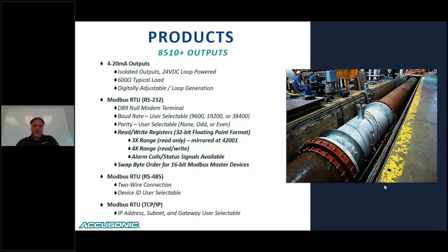The most popular is probably RS-232. It is a DB9 null modem terminal. The baud rate is user selectable between 9600, 19.2, and 38.4. Parity is also selectable. And everything here that's shown in bold applies to whether it's RS-232, 485, or TCP/IP. So every one of those protocols, we have read-write registers. It is in 32-bit floating point format.